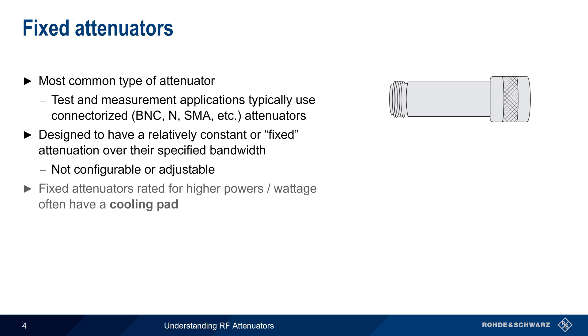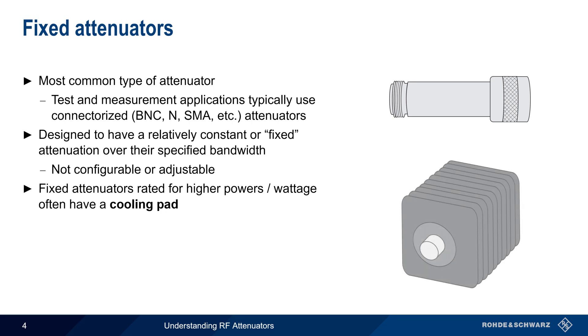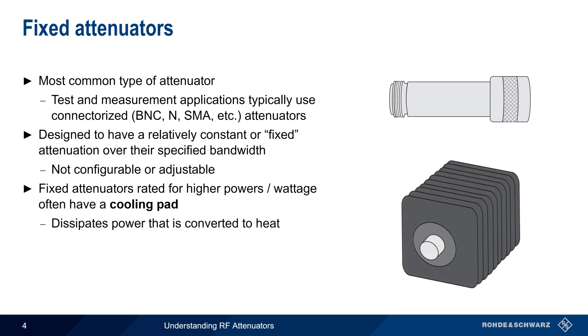Fixed attenuators that are designed for high power or high wattage applications will often have a cooling pad, or fins, that help to dissipate heat.